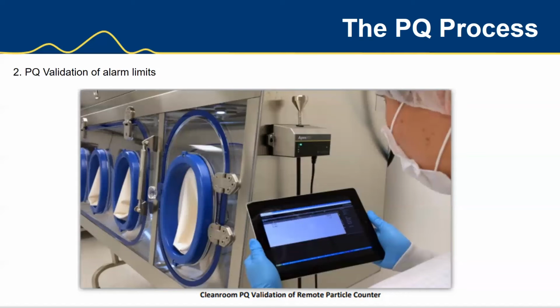Most likely you will see that the impact from the operator has occurred because he's got skin particles floating around there and onto the surface because he's not properly gowned up. In fact, what I would do is when your alarms are triggered in the real world, have the operator that will be intervening, if need be, check themselves. Make sure that there are no holes or rips in the gloves, or that their sleeves aren't exposed. And then they could put into the notes in the audit trail that they acknowledged the alarm and that they checked themselves and weren't seen to have any exposure.